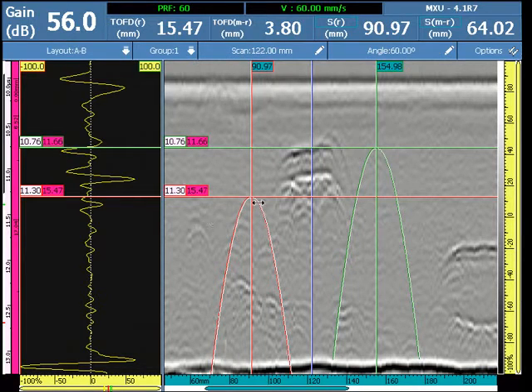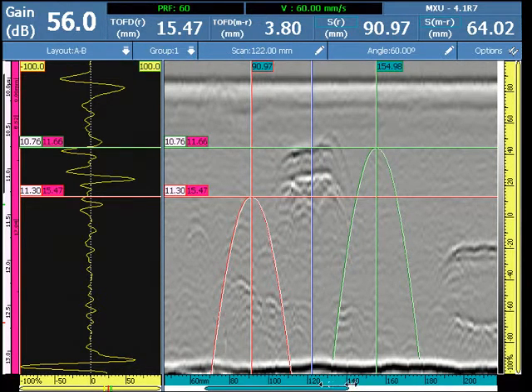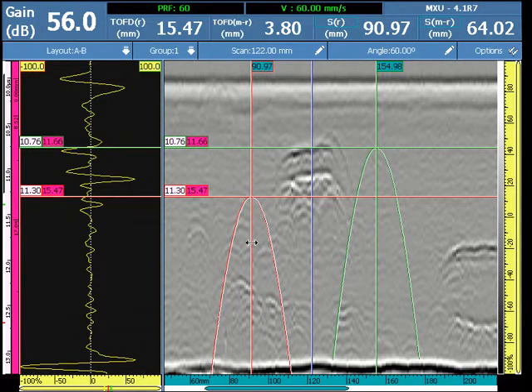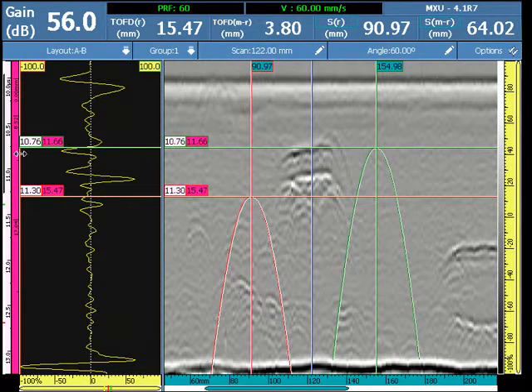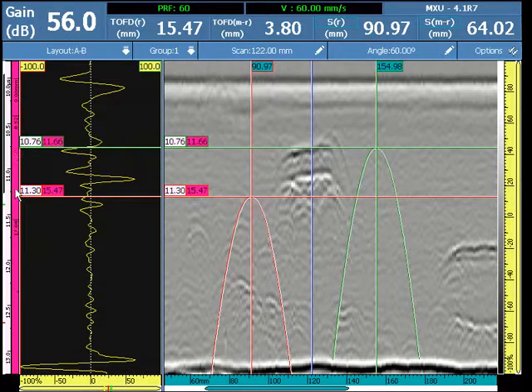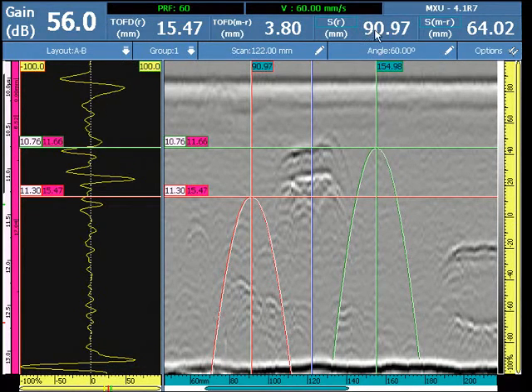The length sizing will be performed on the scan axis and represents the area inside the two cursors on the scan axis. Depth and height are performed on the TOFD or UT axis. Those readings and statistics are available in the header and will be saved in the report.